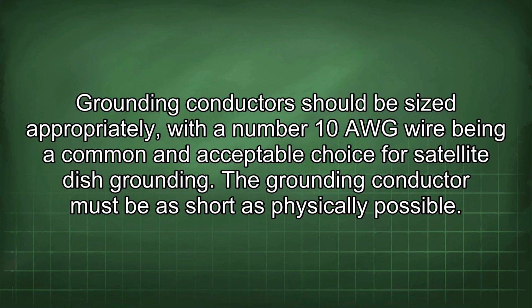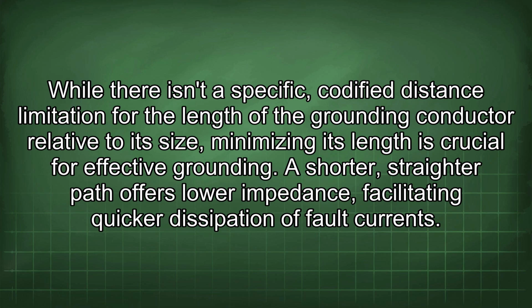The grounding conductor should be sized appropriately, with number 10 AWG wire being a common and acceptable choice for satellite dish grounding. The grounding conductor must be as short as physically possible. While there isn't a specific, codified distance limitation for the length of the grounding conductor relative to its size, minimizing its length is crucial for effective grounding. A shorter, straighter path offers lower impedance, facilitating quicker dissipation of fault currents.